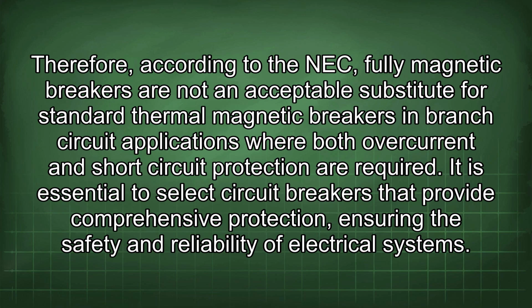Therefore, according to the NEC, fully magnetic breakers are not an acceptable substitute for standard thermal magnetic breakers in branch circuit applications where both overcurrent and short-circuit protection are required. It is essential to select circuit breakers that provide comprehensive protection, ensuring the safety and reliability of electrical systems.